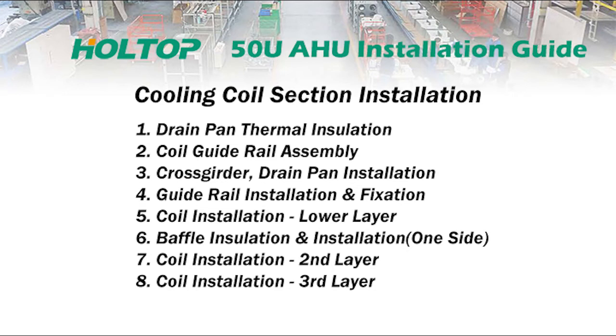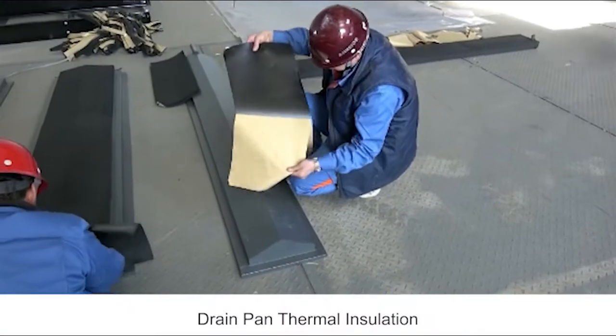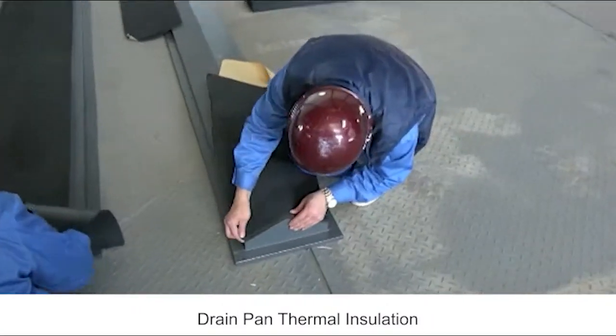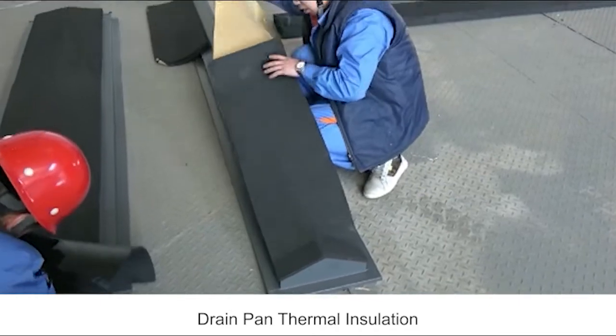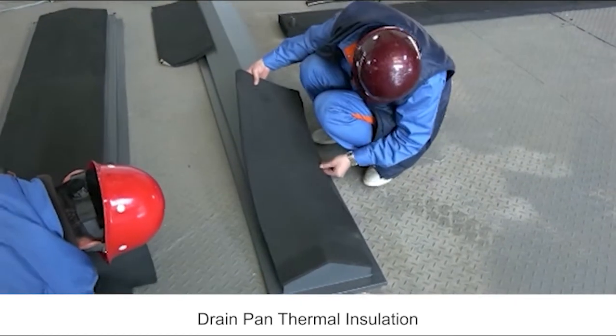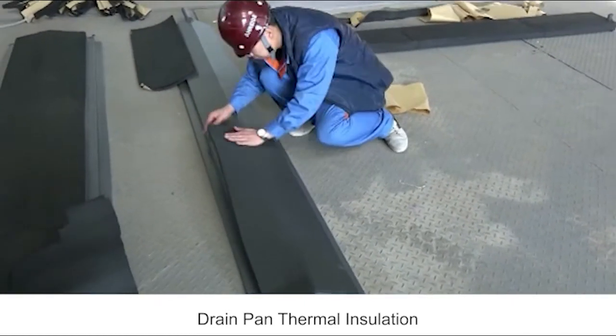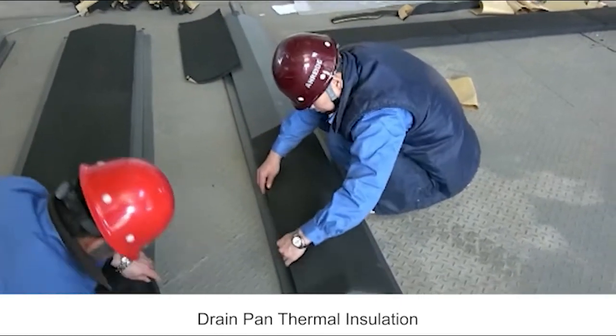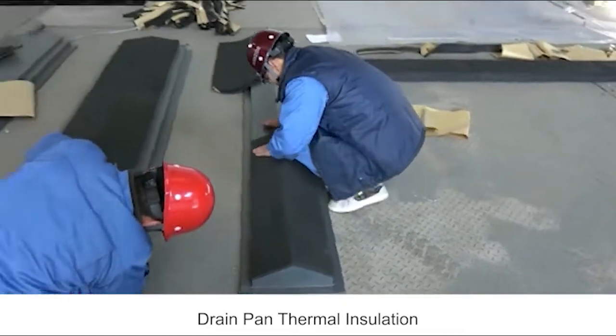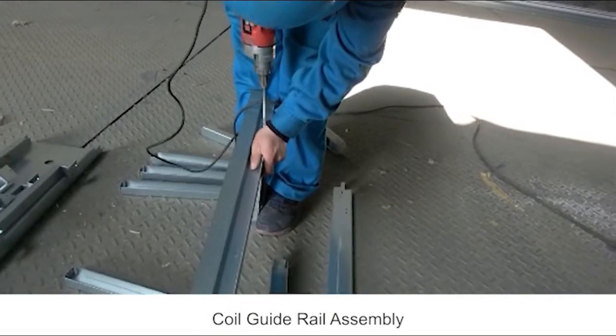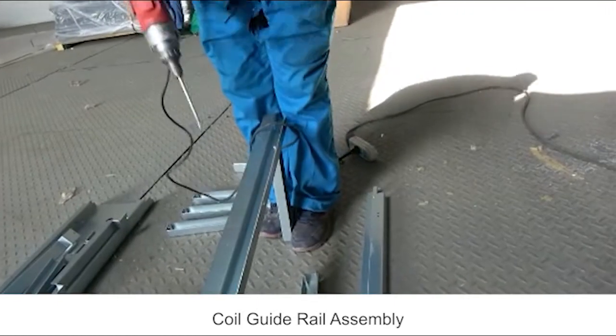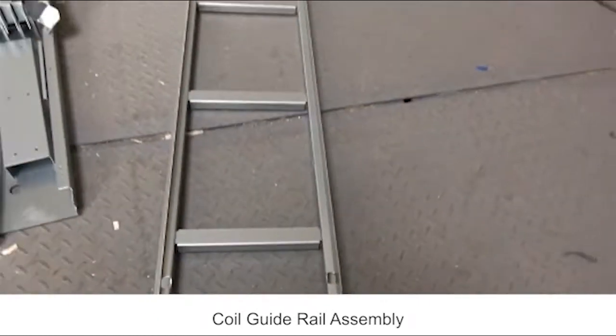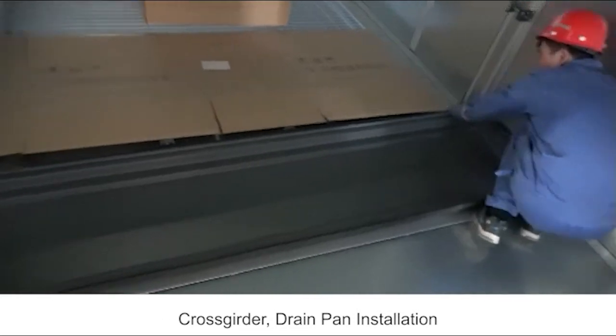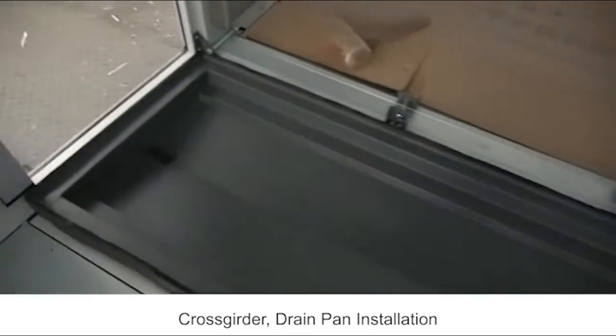Guideline for cooling coil section installation. First, we need to add drain pan thermal insulation. Second, is the coil guide rail assembly. After coil rail assembly completed is the cross girder, drain pan installation.